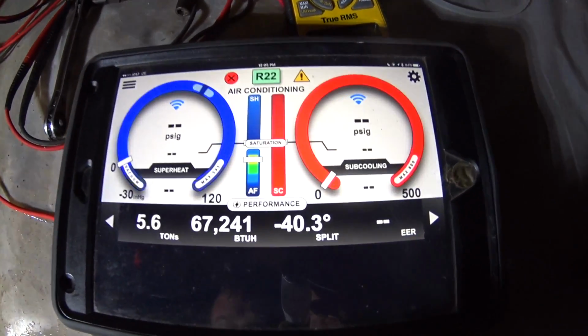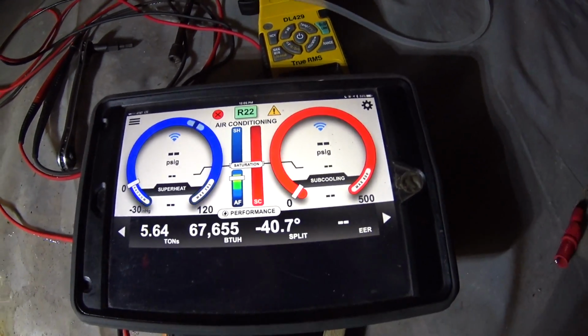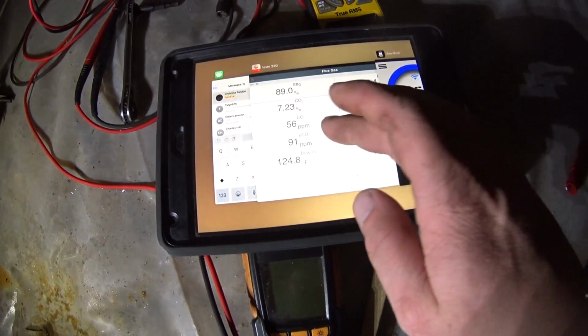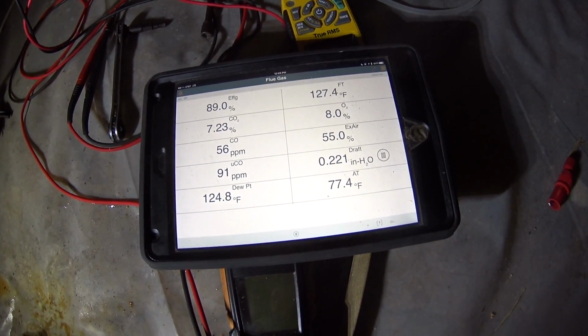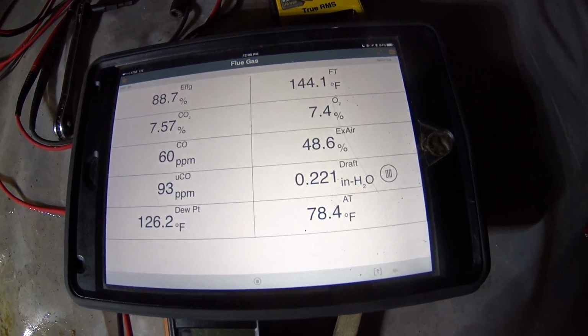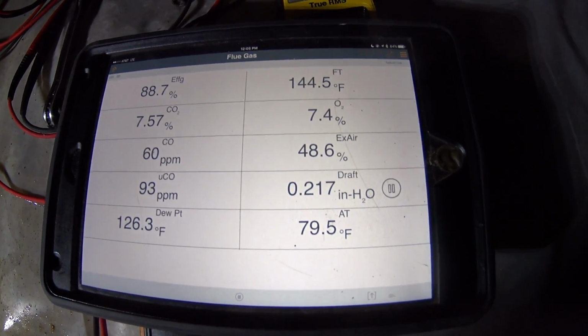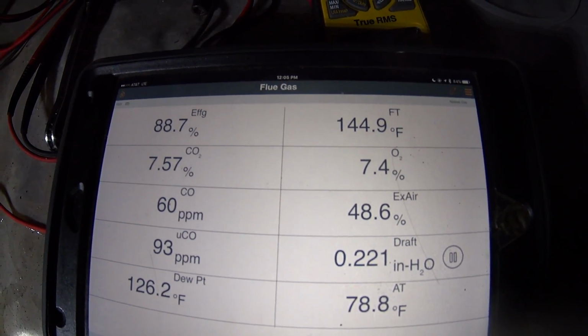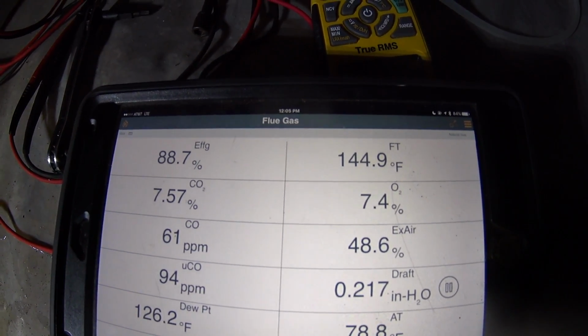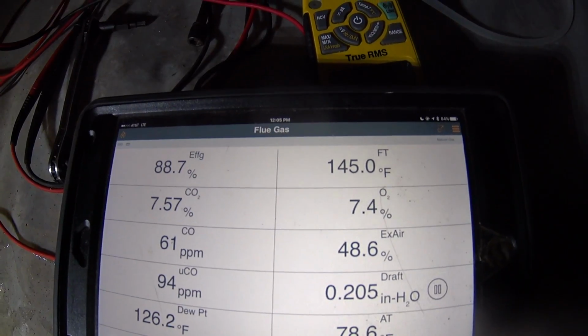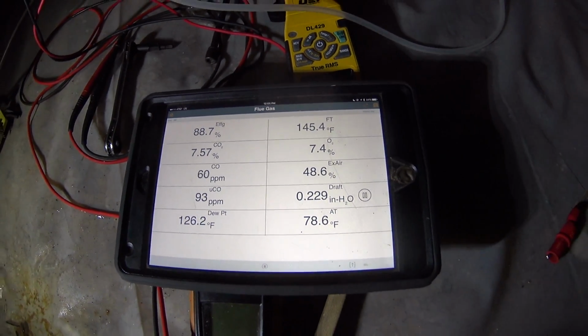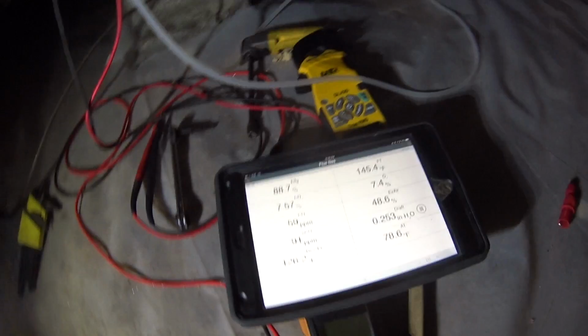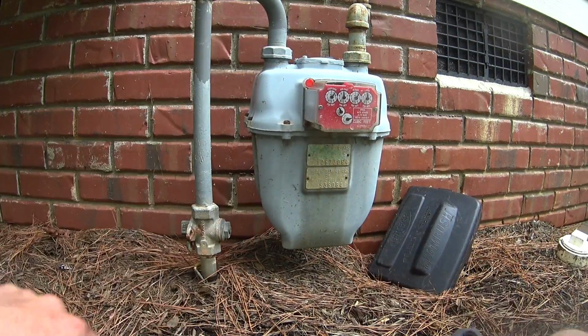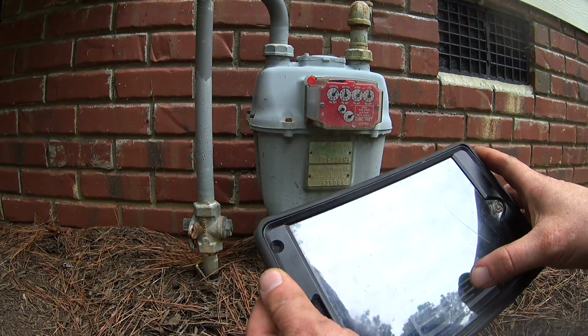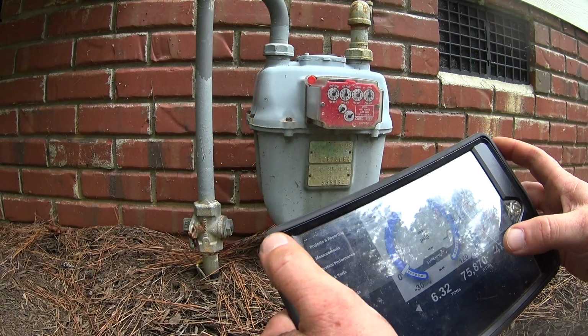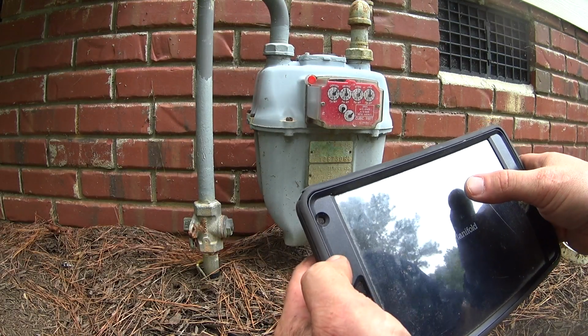We're up to a 40-degree temperature rise. Combustion is showing 49 excess air, 7.57 and 7.4. So I think we're gonna go clock the meter. I can't find a good view here, so we're gonna go with what we've got.